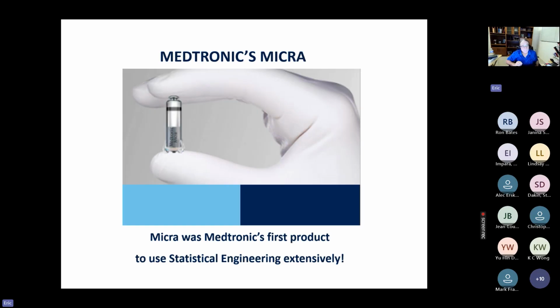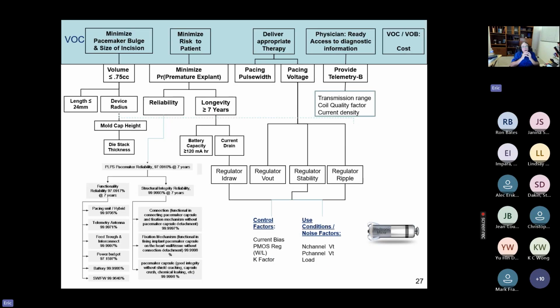So, a micro pacemaker that goes inside the heart. We gathered the voice of the stakeholders, the customers, electrophysiologists, cardiologists, and so forth. That's shown at the top in blue. We translated them into measurable requirements and flowed them down, and this is the flow down you're seeing over here. I'm going to show you a little bit of it. Let's start on the left-hand side. This has to be very small because this is a pacemaker that's going to go inside the heart.